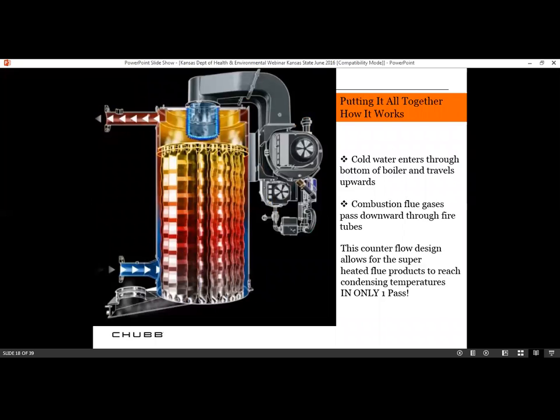This is a schematic drawing of probably a Fulton. This is a hot water system. It could be a Fulton boiler. There's several manufacturers. Lochinvar actually makes one of these too. But if you put it all together, this is how it works. Cold water enters the bottom of the boiler and travels upward. It's sort of a reverse counter design. And then your combustion gases flow down through the fire tubes. This is a counter design, and it allows for superheated flue products to reach condensing temperatures in only one pass.